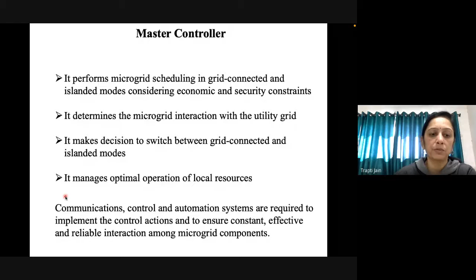Once this microgrid has started operating in islanding, or once islanding happens in the microgrid, the frequency of the microgrid will increase or decrease depending upon the power imbalance in the microgrid. Once the event which caused this isolation disappears, the microgrid needs to be reconnected or resynchronized back to the utility grid.